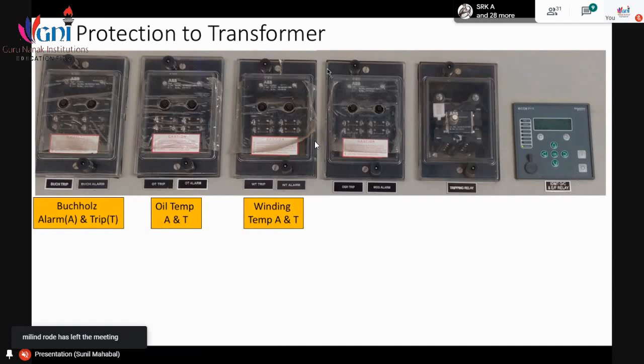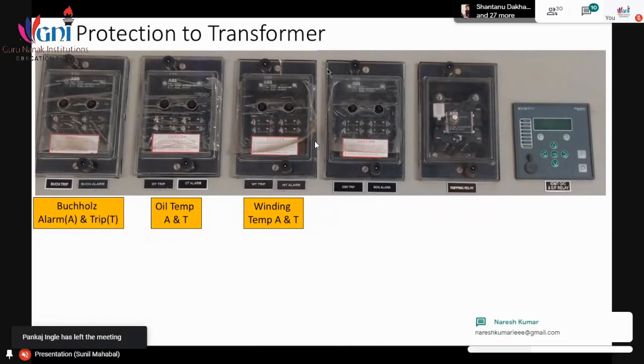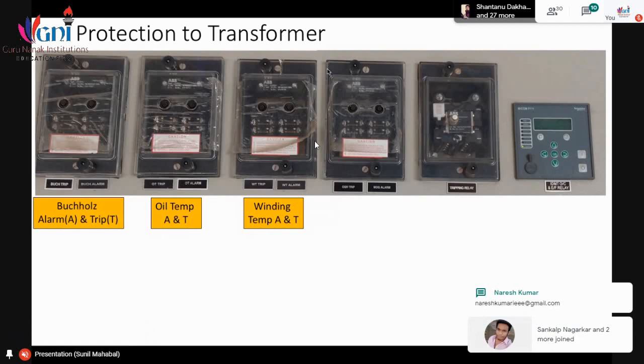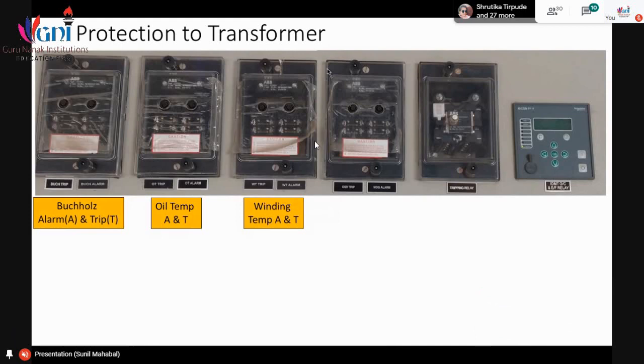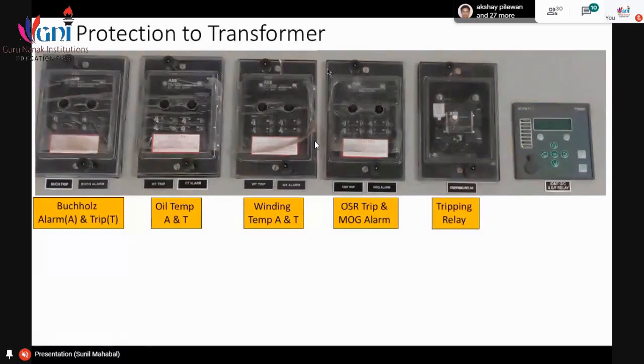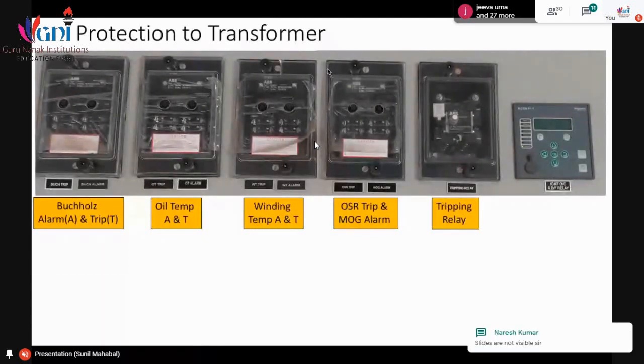Then there is the MOG alarm. In the magnetic oil gauge which we have seen, the inside part is the float, and the outside part is non-magnetic, but an iron part is there. It moves because of the magnet inside. So that relay will trip for this MOG. And these four different relays have alarm and trip. If any one of them trips, then finally all these relays will operate a tripping relay, and this will ultimately trip the 33 kV VCB.